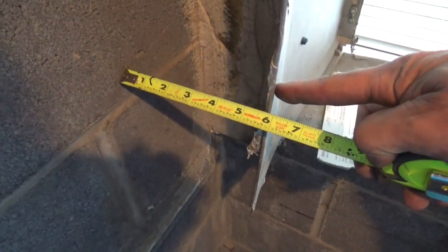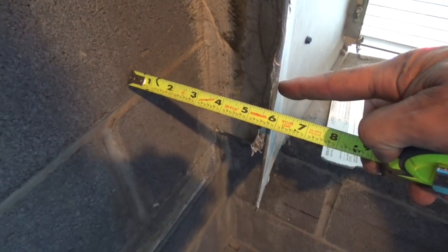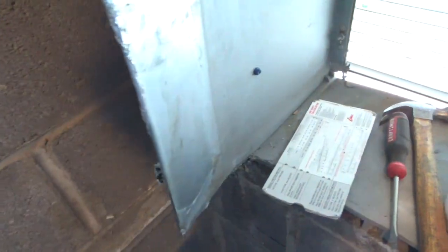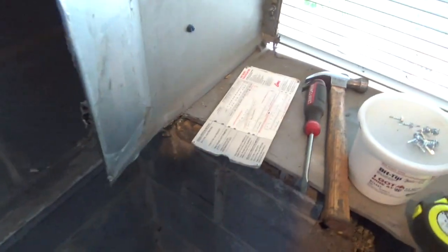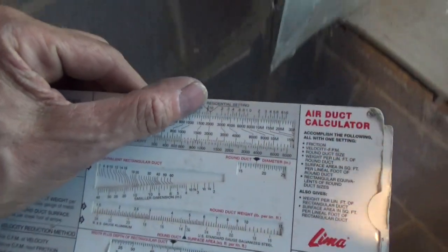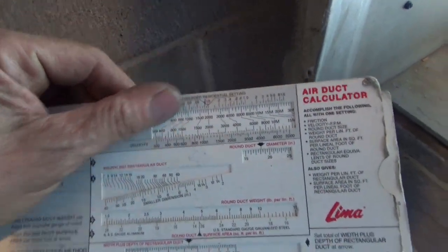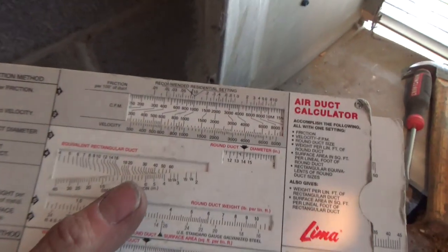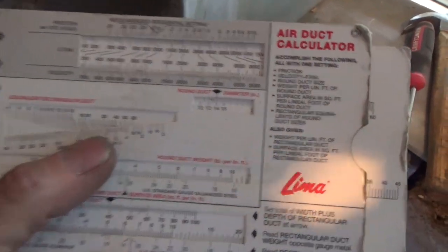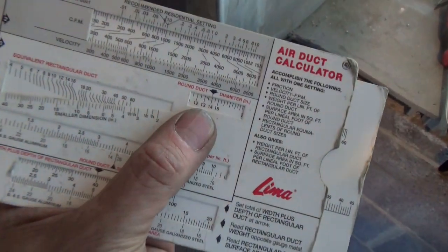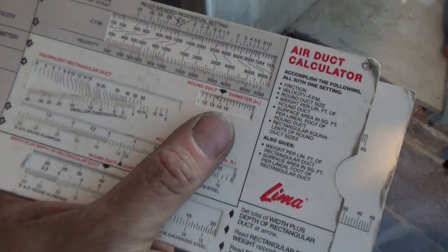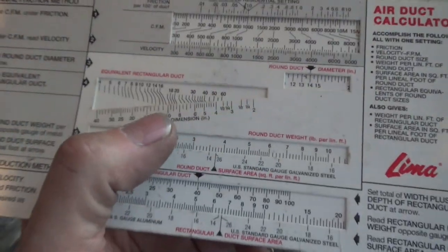Realistically, with the insulation, I'm going to have 5.5 inches. And it's 400 CFM per ton, so I need 1,000 CFM. And I'm using the 1/10 of an inch drop per 100 feet. So the ductulator is adjusted for 1,000. That would be a 14-inch smooth round or a 16-inch flex. This flex has a drop. So I am going to use a short piece of flex that goes straight across the bottom.